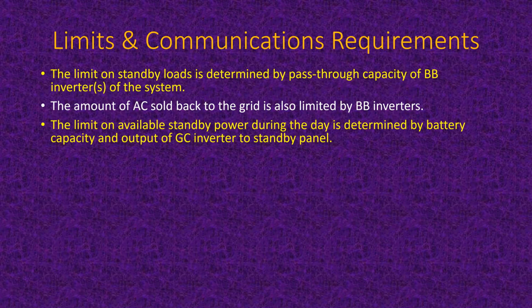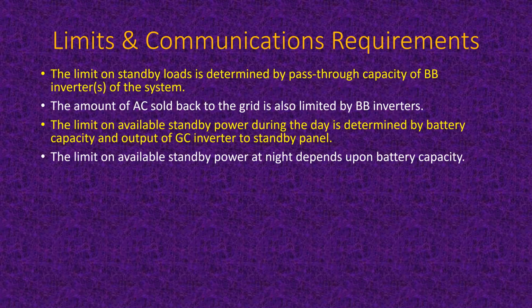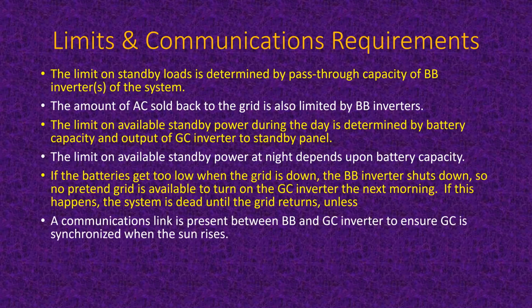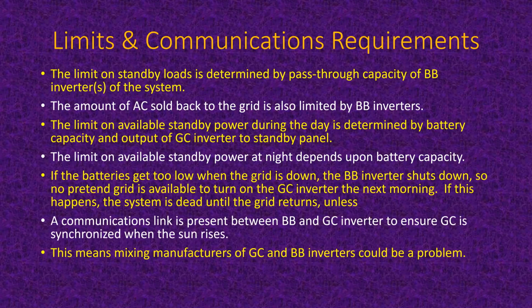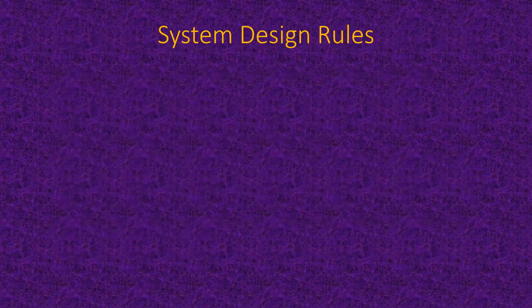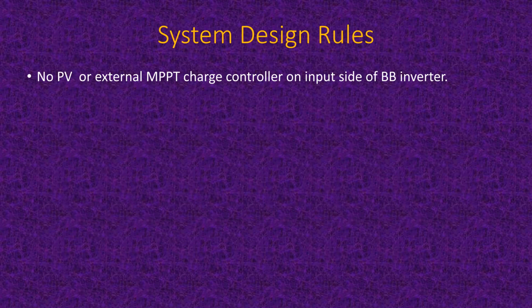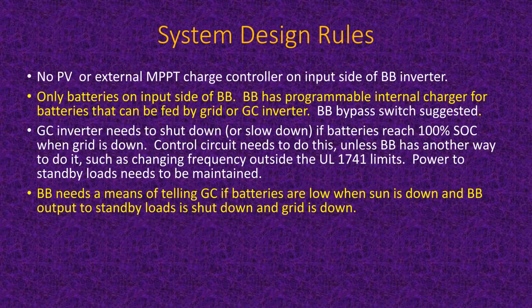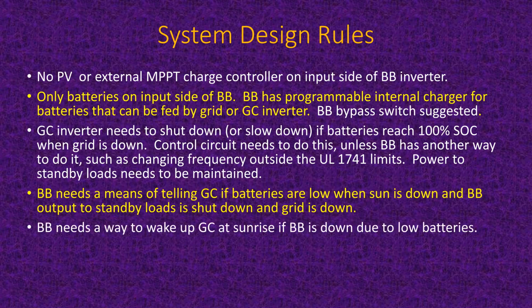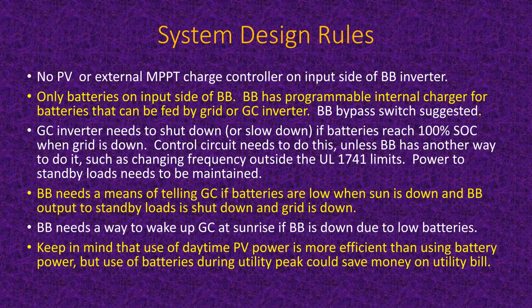The limit on available standby power during the day is determined by the battery capacity and the grid connected inverter to standby panel. And so here are your limits and stuff that are kind of useful to know about. All right, and you'll have this if you get it. Here are your system design rules. And you may not be able to read it that fast, but again, if you're really interested, then order up the slides and you can sit down and have a look at them at your leisure. And there's reference material available as well that can be read to get even more background. Manufacturers have some pretty good stuff out.